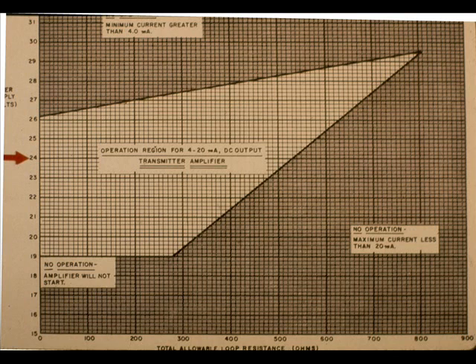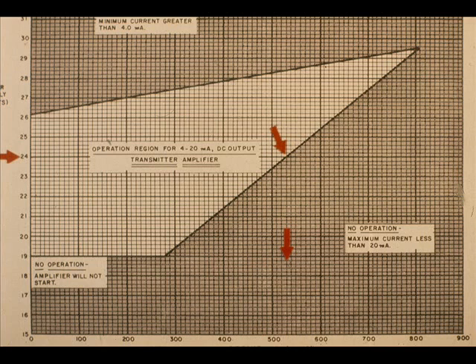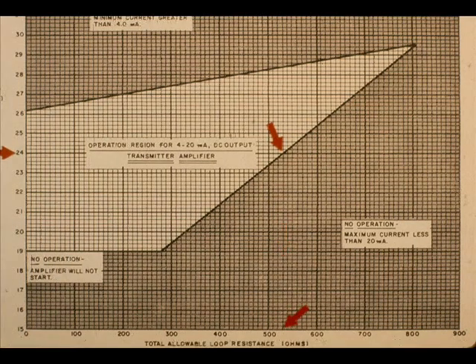The total allowable signal wire resistance for a Veritrac transmitter can be determined from this graph. Locate the number 24 in the volts column on the left side of the graph. Follow the 24 volt line horizontally to the right until it intersects the shaded section. Then from the intersection downward to the bottom of the graph. The line crosses the ohm scale at 530 ohms. 530 ohms is the total allowable loop resistance for the 24 volt DC power supply.